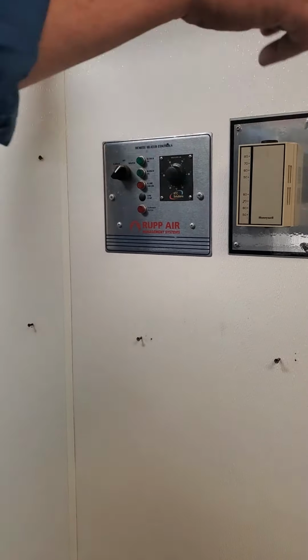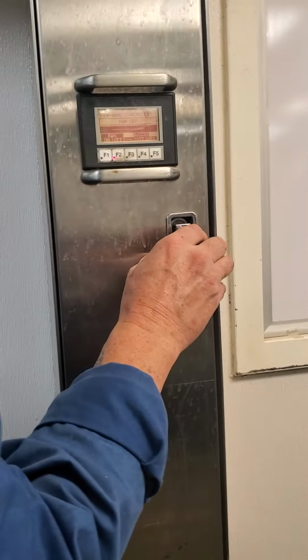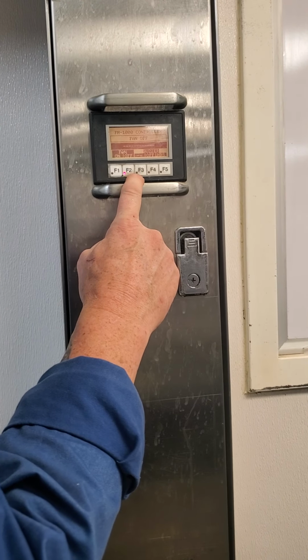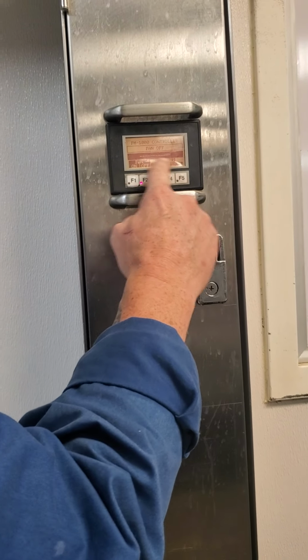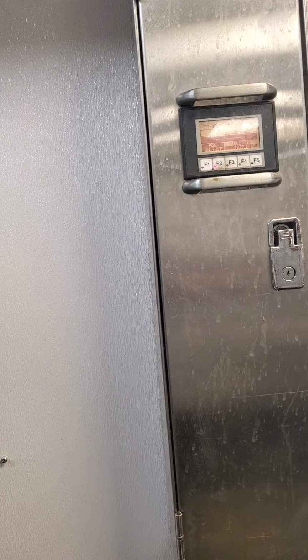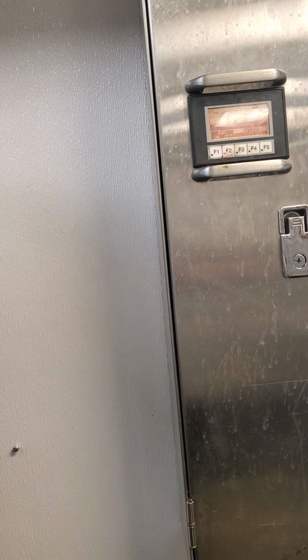This is like an internal controller for the scrubber. There'll be alarms that come up. There's a pressure switch in between each bank of filters out there. I used to test it all the time - I have it so unsensitive that the filters could get plugged on that scrubber.